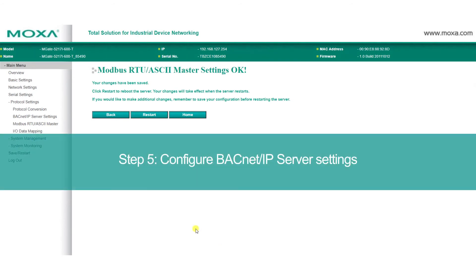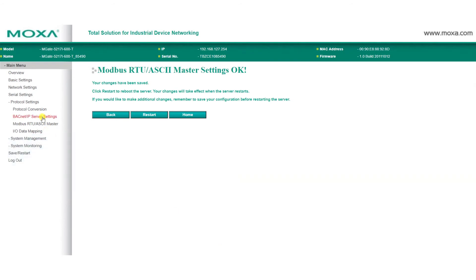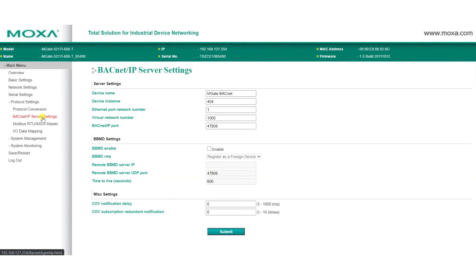The MGate will also act as a BACnet IP server, and in BACnet IP server settings, you can configure basic parameters, such as device name, device instance, and the BACnet IP port.